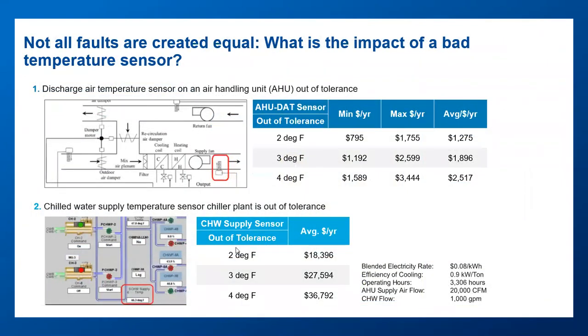This is just an example looking at one type of fault, the easy to understand kind. You have more system level faults as well as device level faults, but what's the impact of a temperature sensor that's out of tolerance by 2, 3, or 4 degrees Fahrenheit? You can see the difference in economic impact of having that problem in an air handling unit discharge air temperature sensor versus a chilled water supply temperature sensor with a 4 degree out of tolerance reading - it's more than 10 times the impact, an order of magnitude difference. So it's really important that these FDD tools do a good job automating the prioritization of faults.